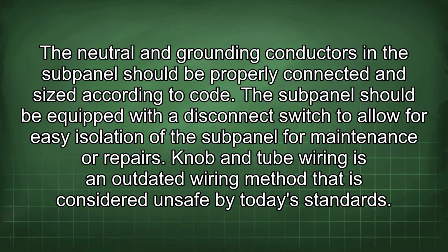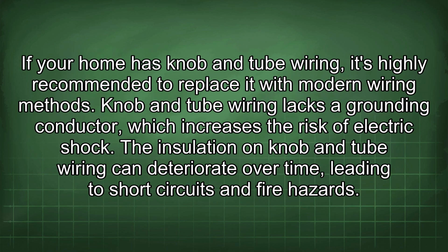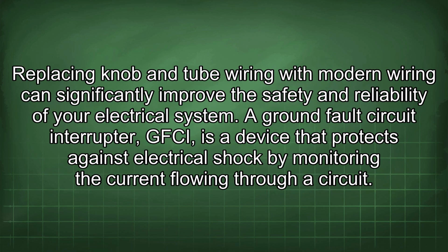The subpanel should be equipped with a disconnect switch to allow for easy isolation of the subpanel for maintenance or repairs. Knob and tube wiring is an outdated wiring method that is considered unsafe by today's standards. If your home has knob and tube wiring, it's highly recommended to replace it with modern wiring methods. Knob and tube wiring lacks a grounding conductor, which increases the risk of electric shock. The insulation on knob and tube wiring can deteriorate over time, leading to short circuits and fire hazards. Replacing knob and tube wiring with modern wiring can significantly improve the safety and reliability of your electrical system.